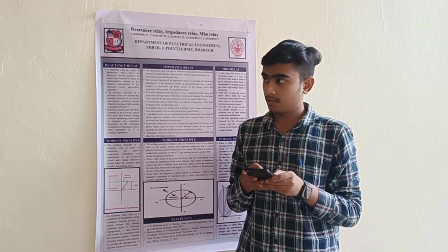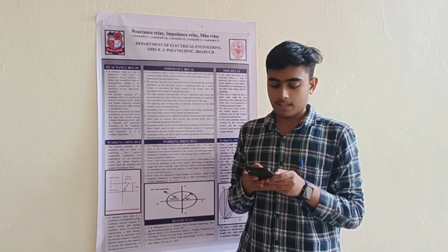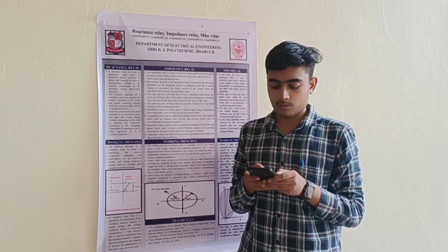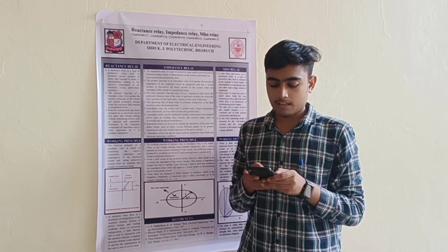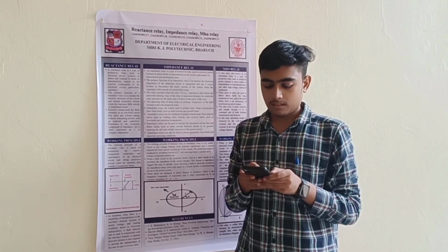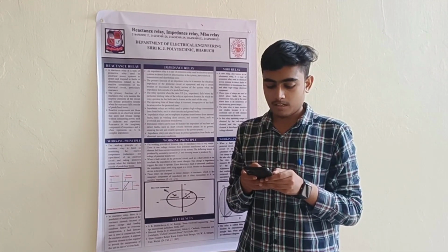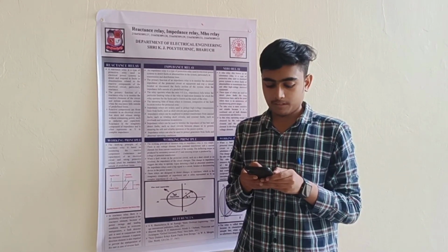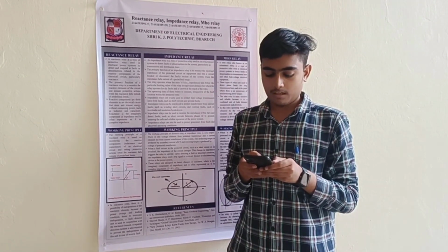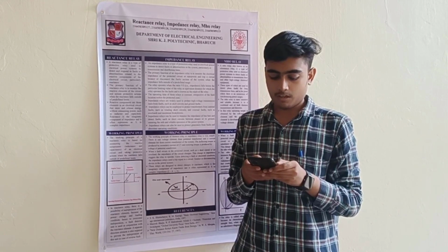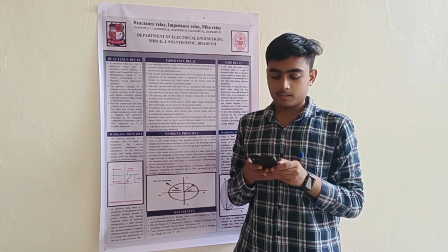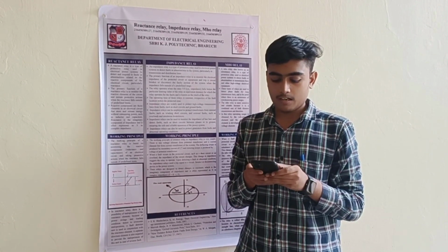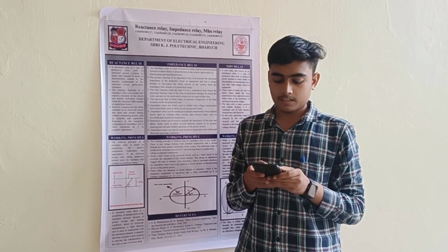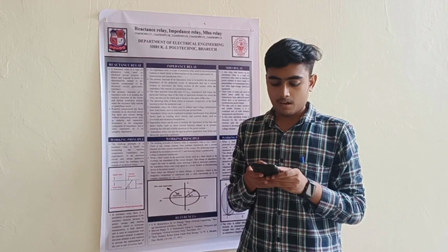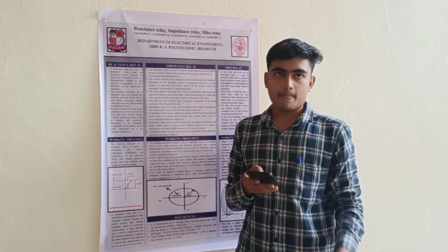Second, zone protection. Mho relays are commonly used for providing zone protection in transmission lines. By setting the relay's impedance reach and angle, a specific section of the transmission line can be protected. When a fault occurs within the reach of the relay, it operates and isolates the faulted section, preventing it from affecting other parts of the system.